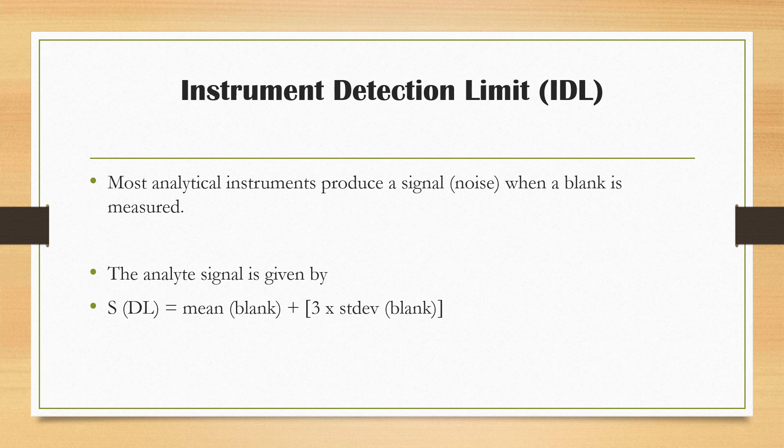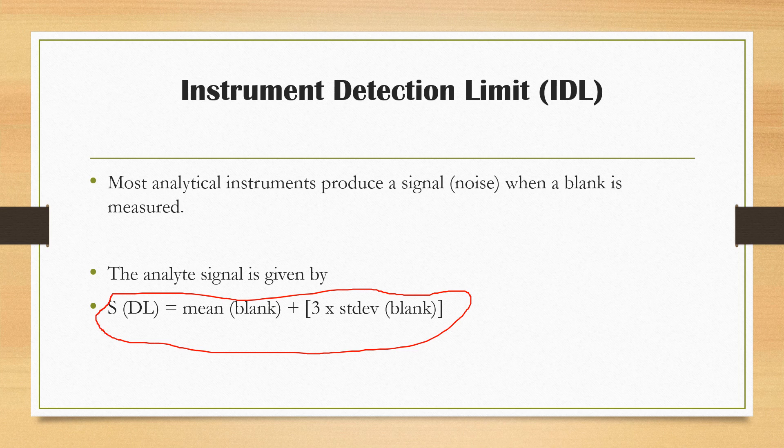You run the blank solution for a couple of times, preferably five to eight times. From the values that you obtain, you can calculate the mean and the standard deviation of your blank solution. Then you insert it into the formula for calculating detection limit to find out the detection limit of that particular analytical instrument. The formula is given as the mean of the blank solution plus three times the standard deviation of the blank solution.